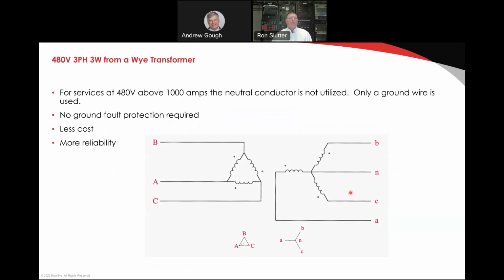Here's what we recommend for you to do to get around all of that and to have a more reliable system and less money. For services that are 480 volt above 1,000 amps, the neutral conductor is not utilized. So we no longer use 277. Only the ground wire is brought from the center tap. So instead of this being the neutral conductor to the building, this is a ground wire, and that's it. There is no neutral to the building. We do this very specifically. No ground fault protection is required when we eliminate the neutral. It's less cost and it's more reliable.